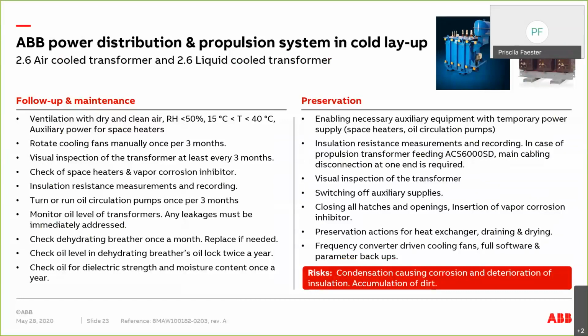For the follow-up and maintenance, the cooling fans need to be used at least once per 3 months. See that all the fans are working, they're running, and there's no strange noise or anything coming out from them, and to have some movements for them. That's mechanical equipment, so they need to move every now and then. Same for liquid cooled transformer, oil pumps, or the liquid pumps, they need to be rotated once per 3 months to put the oil inside the transformer moving.